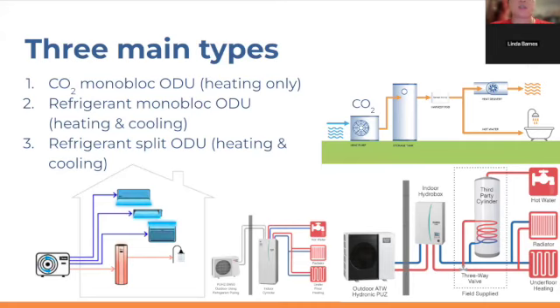In the case of CO2, it's not super important whether it leaks or not, because CO2 has a global warming potential of 1, and all the other refrigerants are indexed to how many times CO2 their global warming potential is. In the case of refrigerant based monoblock outdoor units, refrigerant meaning anything other than CO2, because it's non-CO2, these systems can typically always do heating and cooling. The common refrigerants in the second category are R32 and R454B.